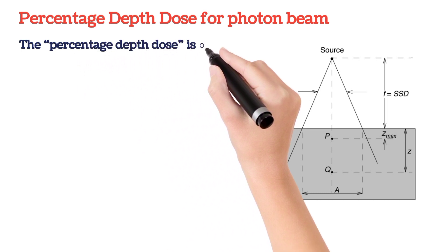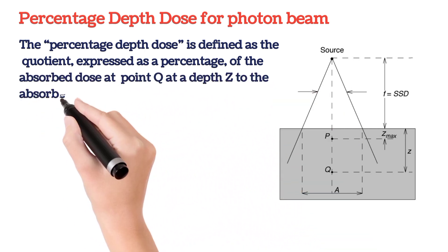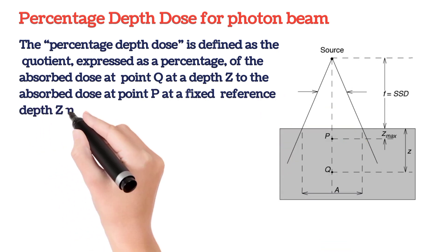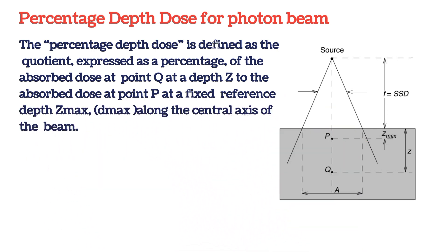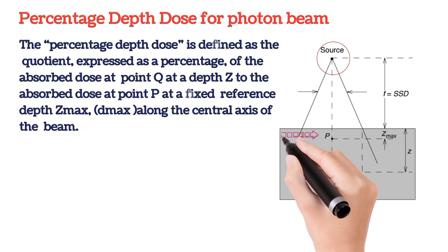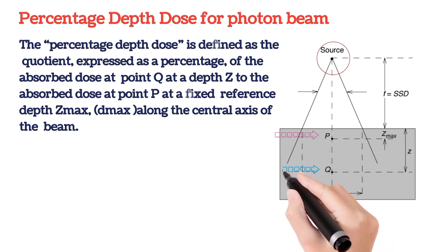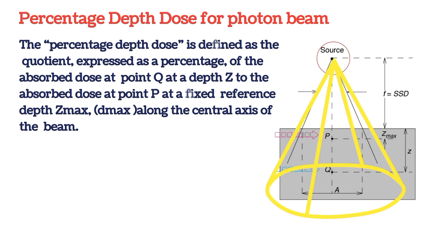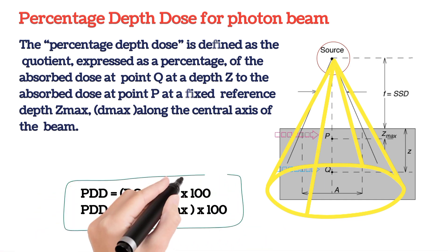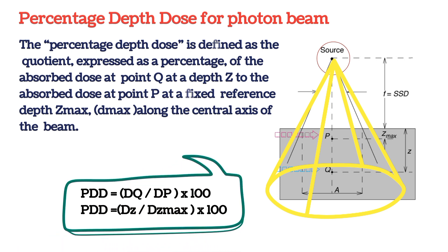PDD is expressed as a percentage of the absorbed dose at point Q at a depth Z to the absorbed dose at point P at a fixed reference depth D max along the central axis of the beam. PDD is simply the ratio of dose at two points at different depths, multiplied by 100.